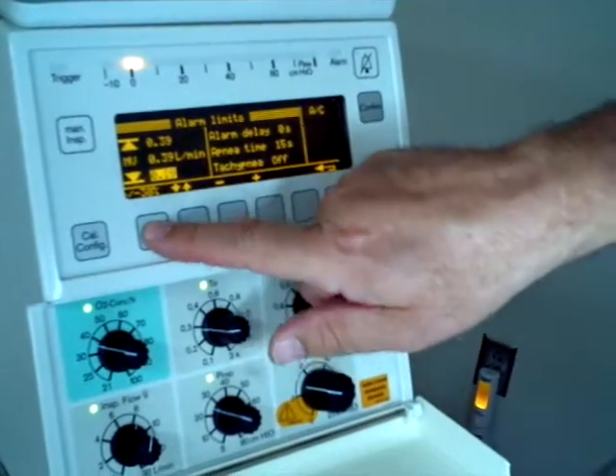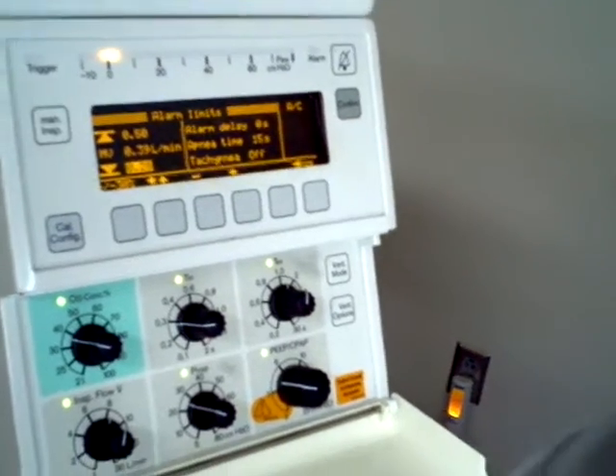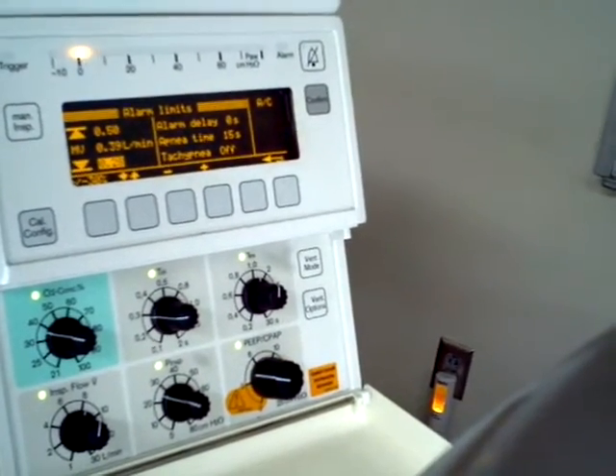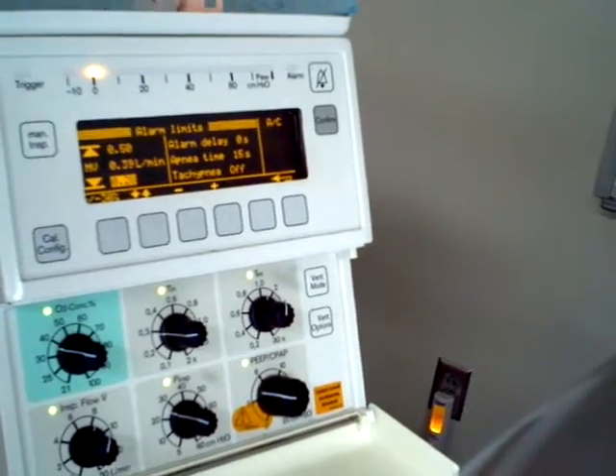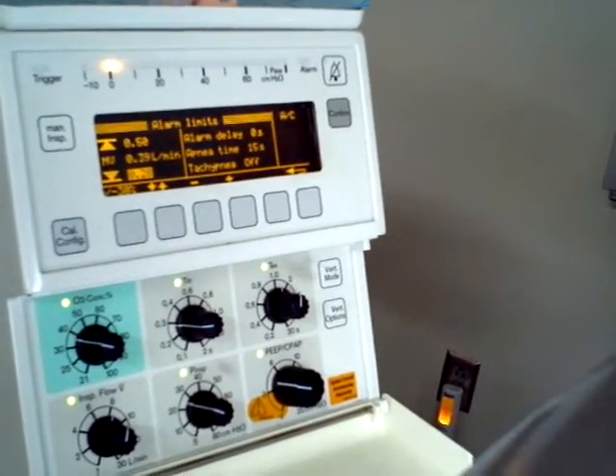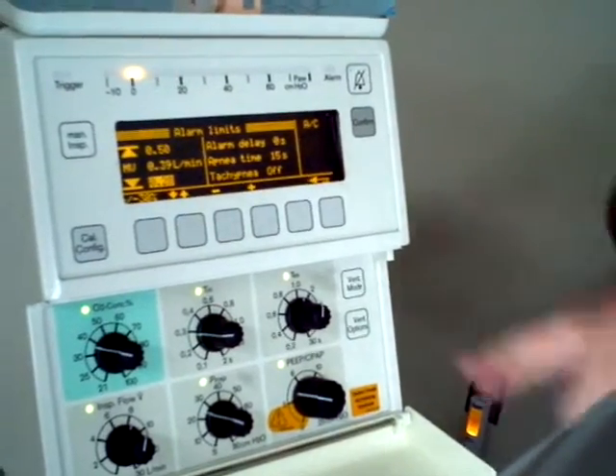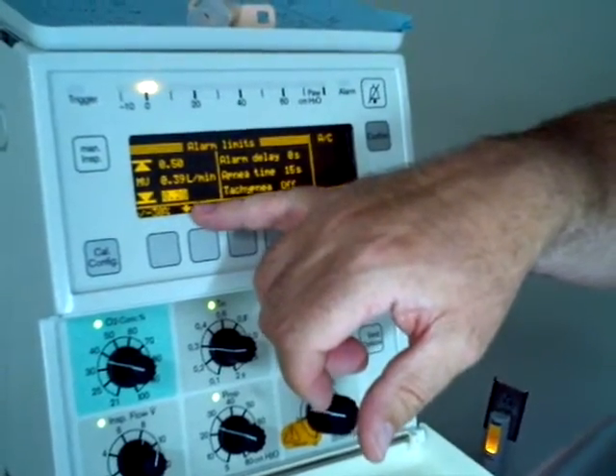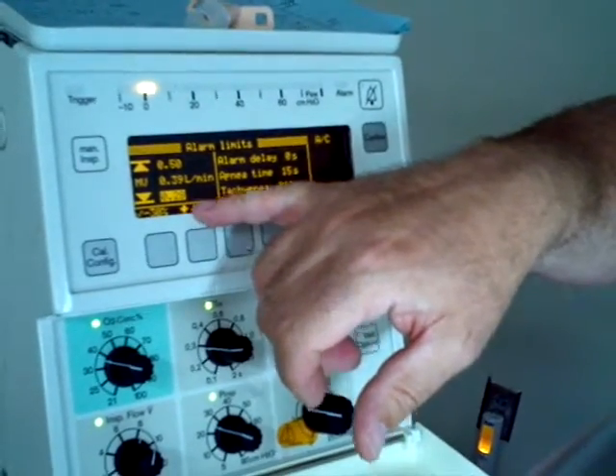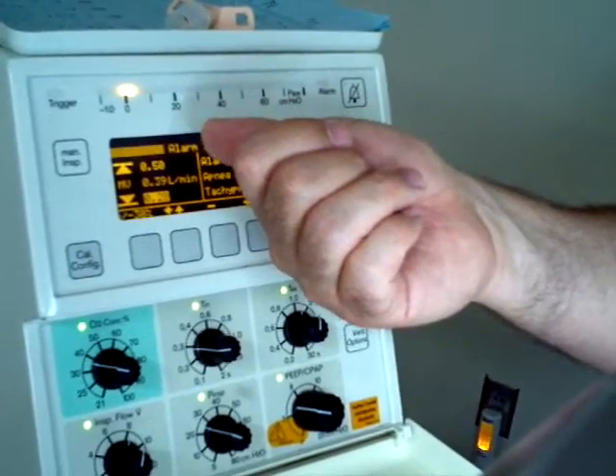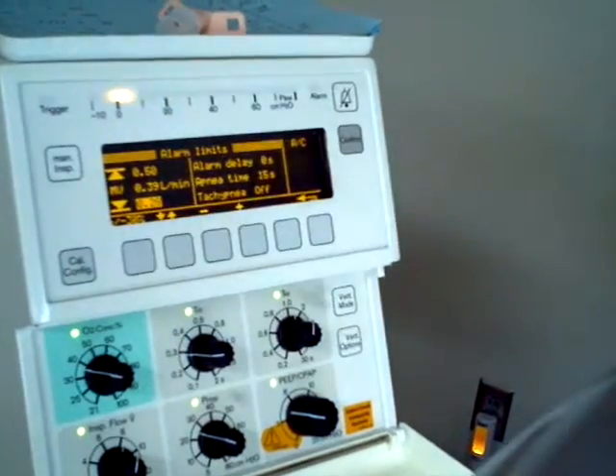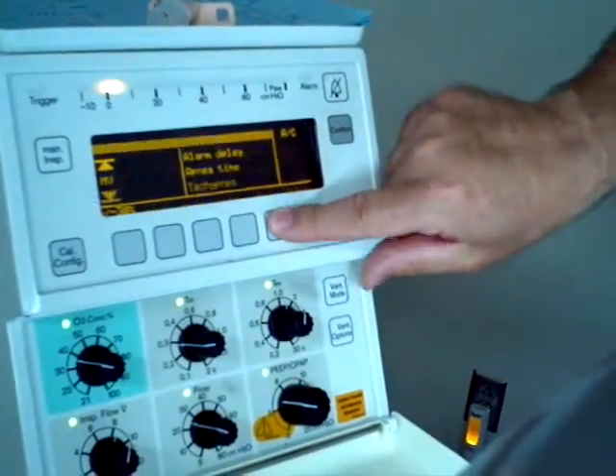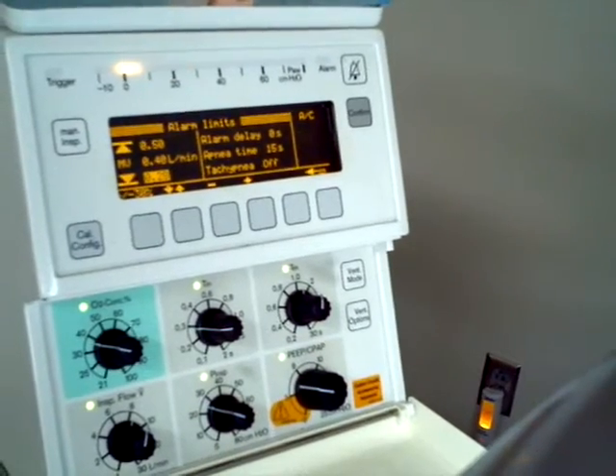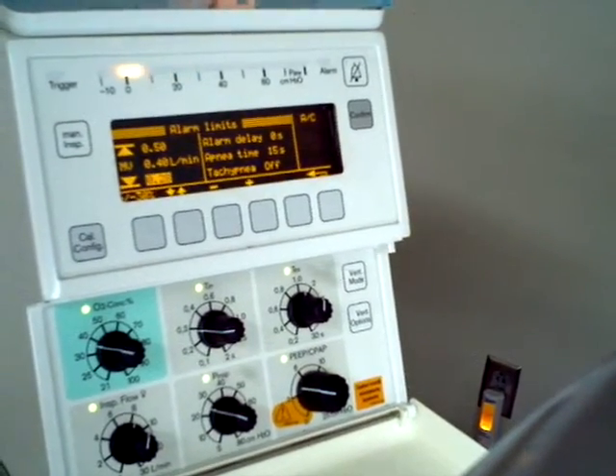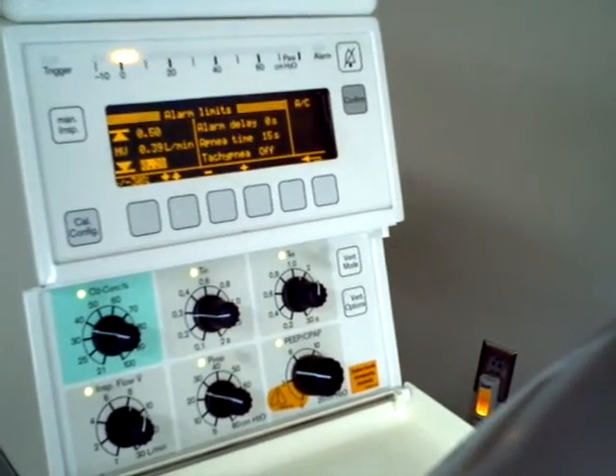There's a handy key here that's plus or minus 30%. That's not a bad place to start. I usually use that as a start and then look at the numbers I have there. Is that a good place to have the settings? In other words, if my baby slows down or we have a leak and it drops below 0.28, is that tight enough? Or if they breathe extra volume, extra rate on their own, is 0.50. I think those are pretty good numbers, really. I think plus or minus 30% is pretty good, at least in this population.